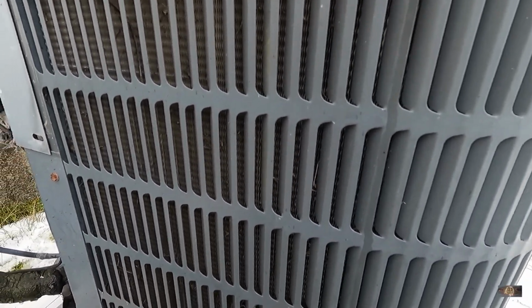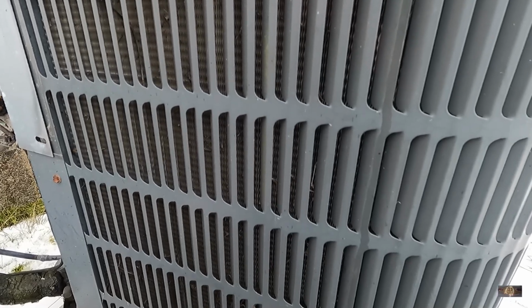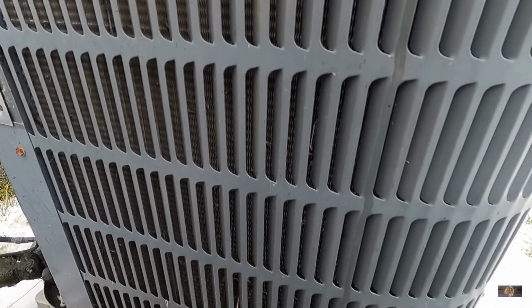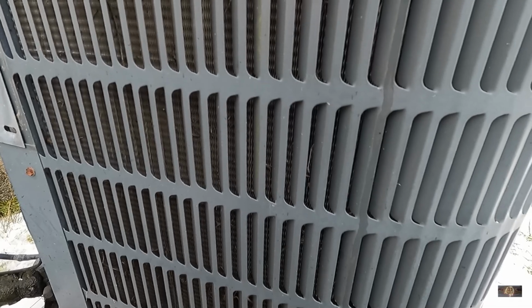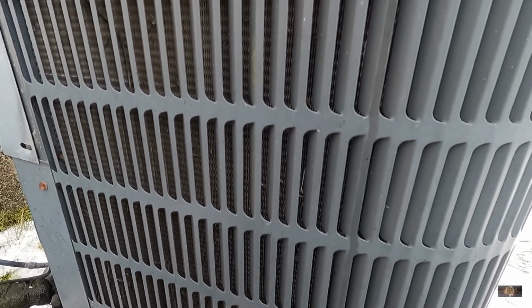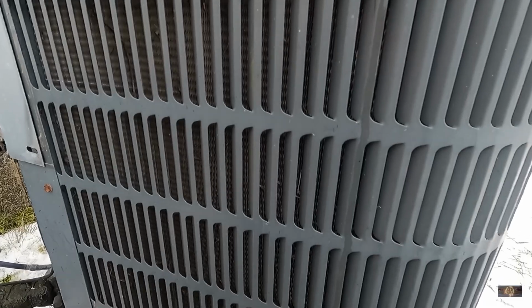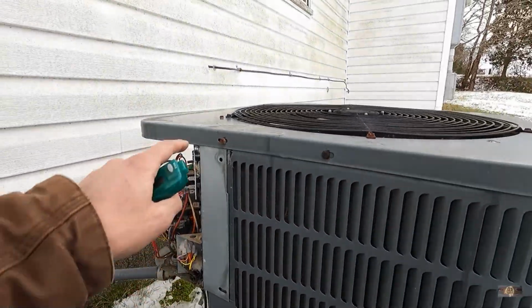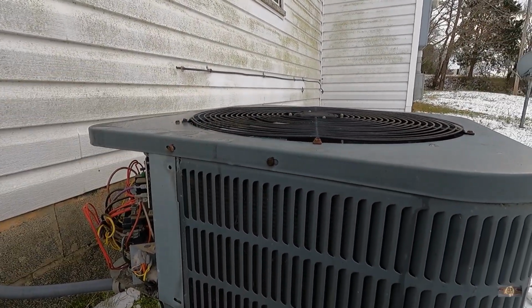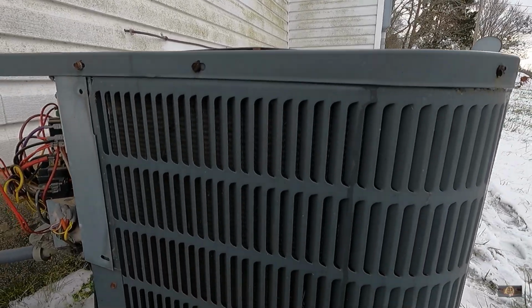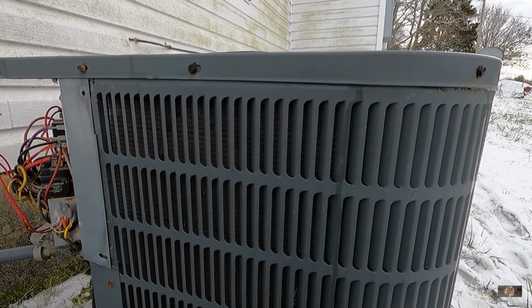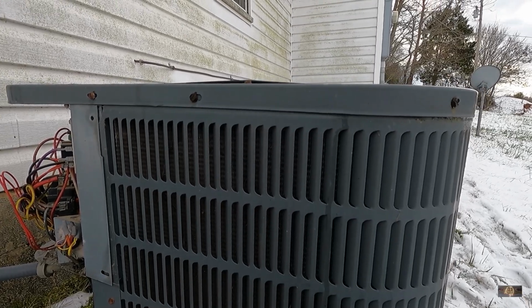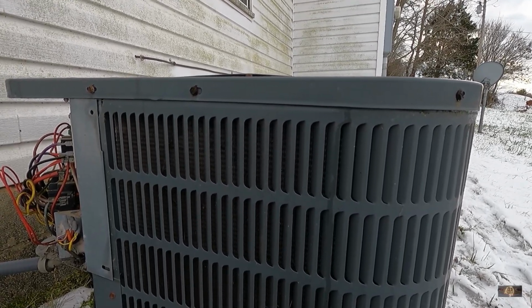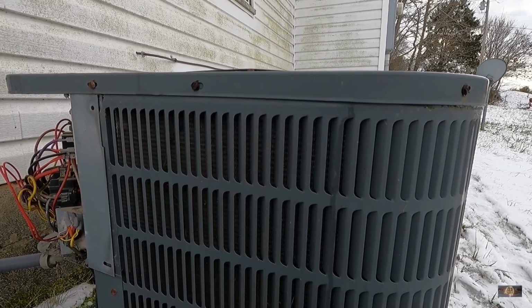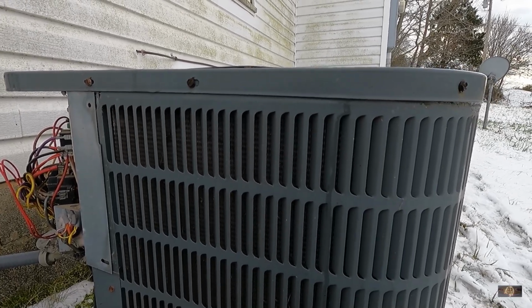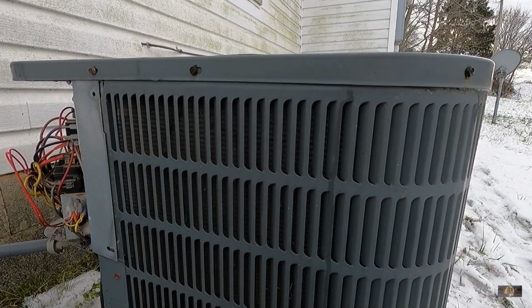So I'm going to let this thing finish defrost, and then I'm going to do another amp draw on this outdoor fan motor. So far, the only thing I've heard on it is the clicking noise. Has not made that clunking noise. I did make them aware of the roof here draining onto their unit, so it is dropping ice right into this thing. There we go, she shifted back. I was gonna see if I heard anything on that fan motor. Nope. Okay, so I think what I'm going to have to do is do another amp draw on the fan motor, see if it's any higher.